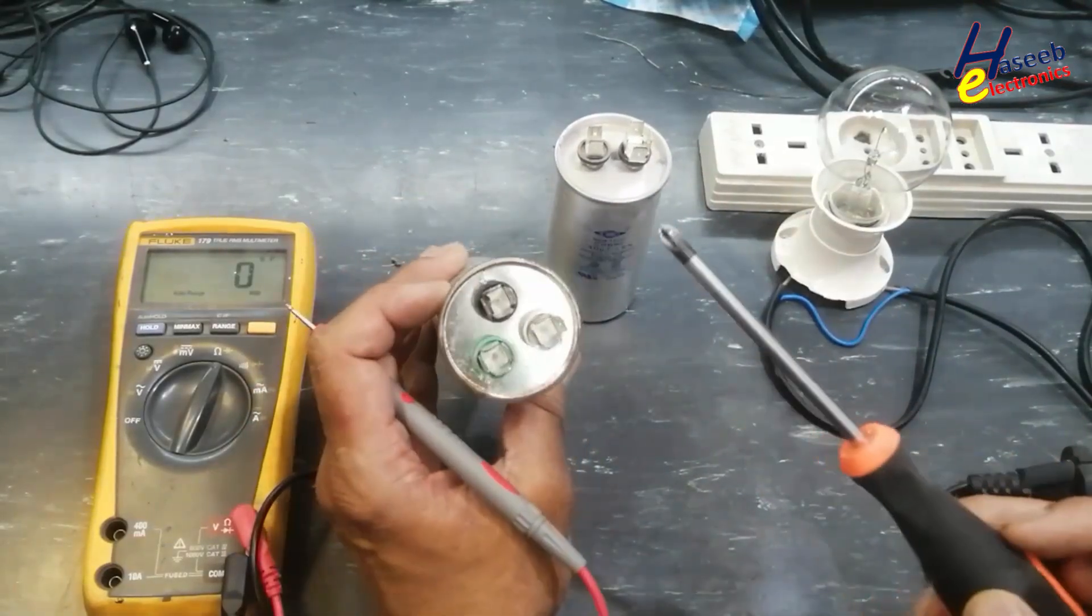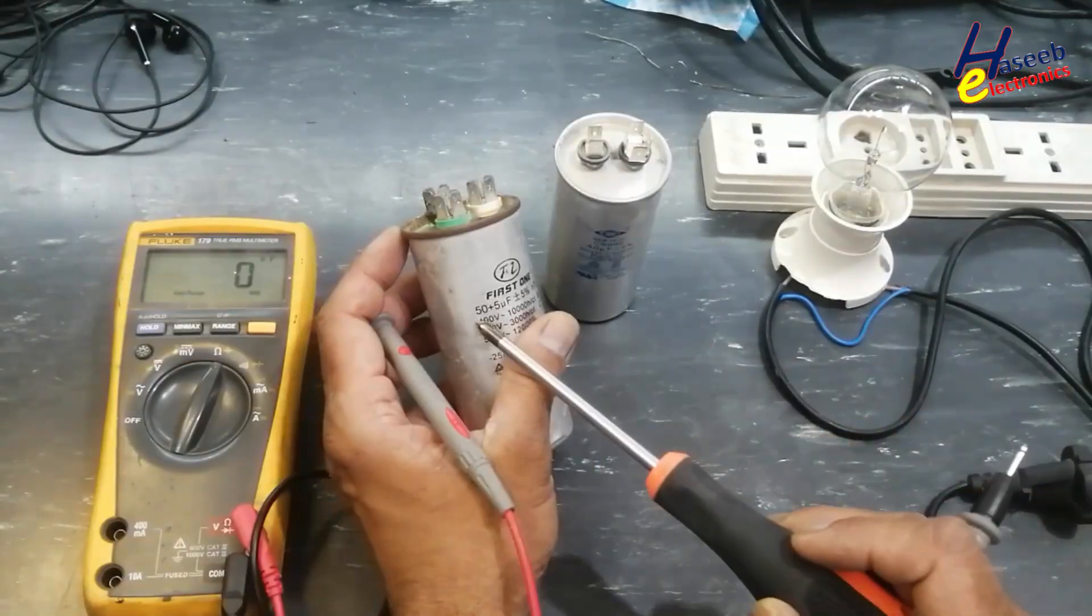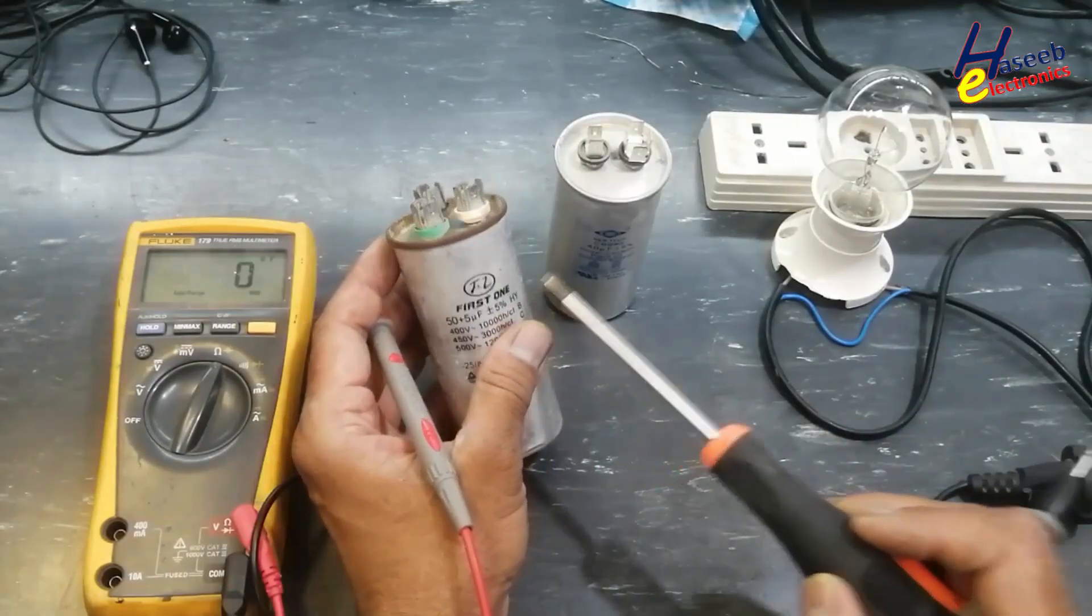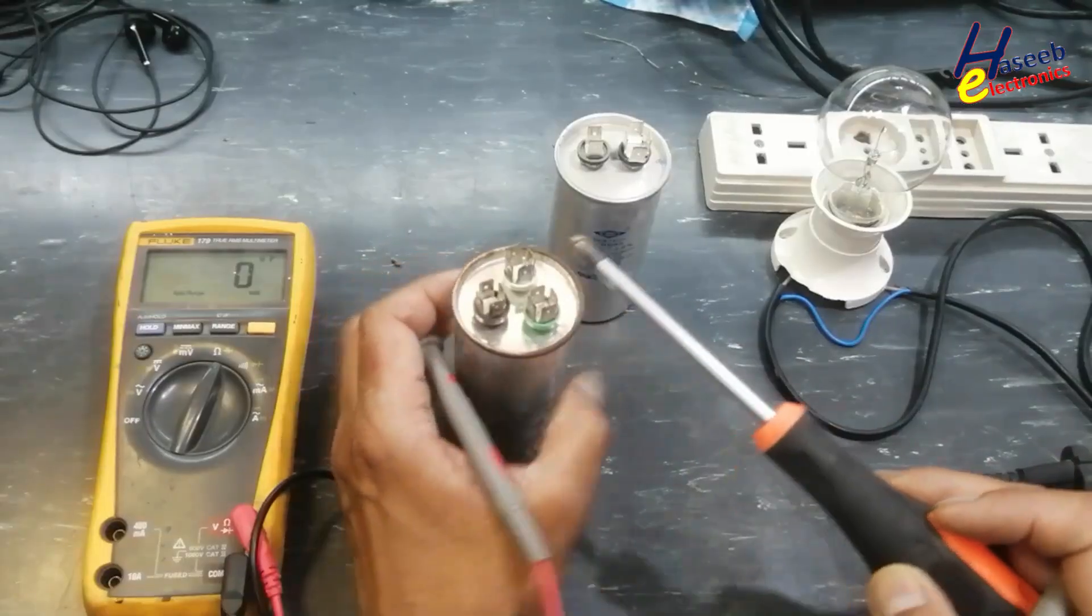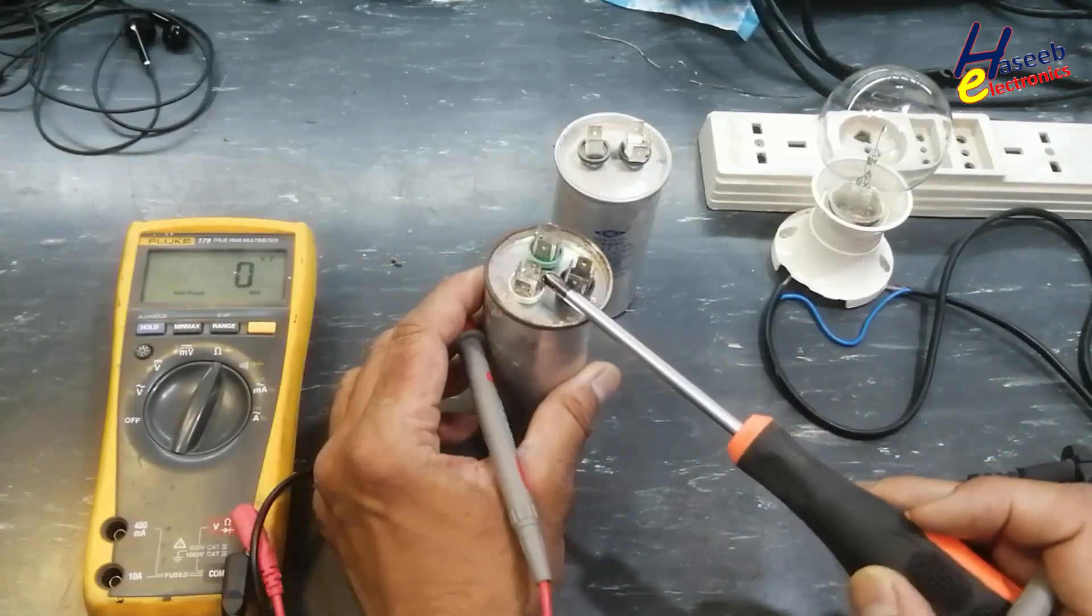Same way, I have a 3 terminal capacitor, 50uF and 5uF. Common and fan, common and compressor.